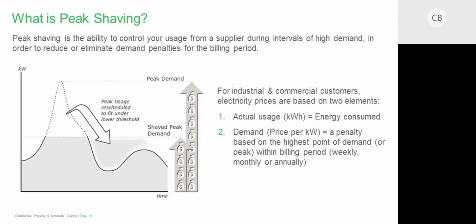So what that means is when they start processing, you're going to see wider variations in the load on that IT kit. And so I think we're going to start seeing a lot more peaks up and down in the data center environment as those servers start cycling and processing. And it may be driven at different times of day, depending on the applications that are running in there. That represents opportunity to do a lot of micro peak shaving in a data center environment. Next slide.